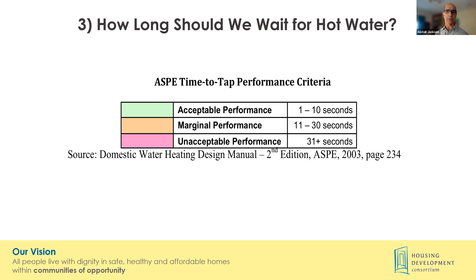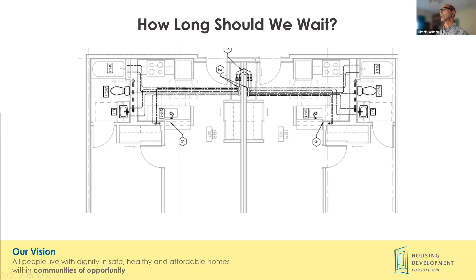Evergreen version 4, criterion 4.06, requires a half gallon of water in the pipe between the recirculation loop and the fixture. So if you have a 1.5 gallon low flow shower head, you're going to wait about 20 seconds for hot water. That's where Evergreen sets the bar. The good news is that getting the stored water volume in a pipe down to or even below that half gallon just takes a little care and attention. Here's an example with 2 stacks of units served off a common riser shared between the 2 units, with plumbing runs in PEX piping across to the bathrooms. In the reverse situation, with the bathrooms on the interior walls together, you can see it improved even more.